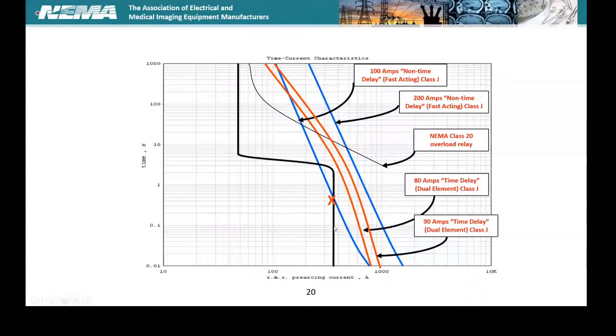We've got a high inrush current. This is our current scale, our time scale. So we've got a startup time and a startup current, and then it levels out and it comes back to our full load ampere rating right here.